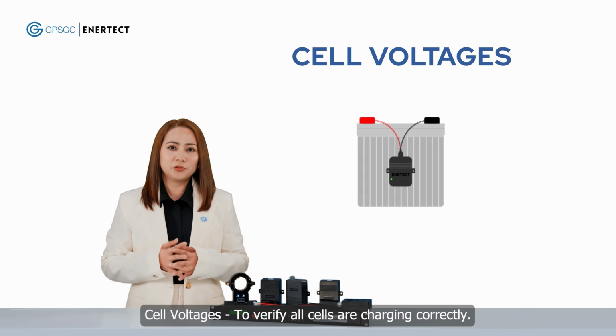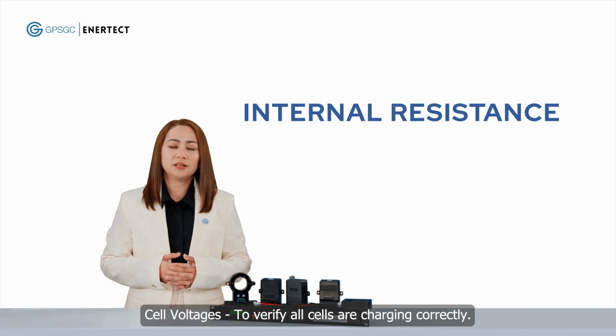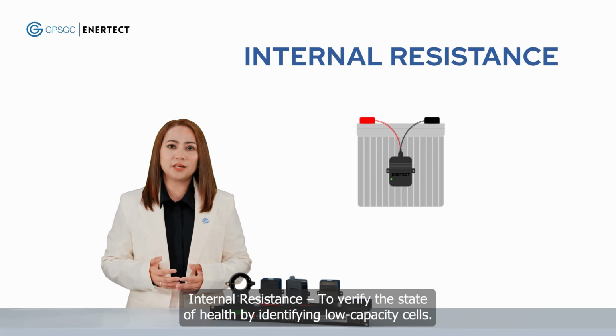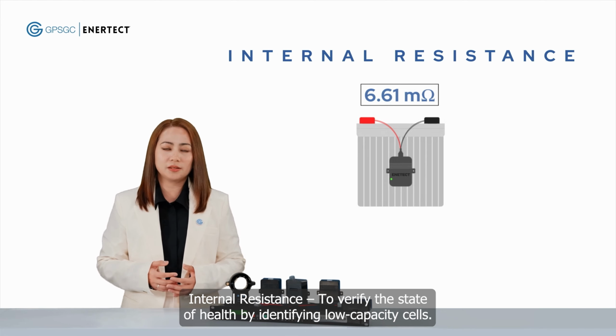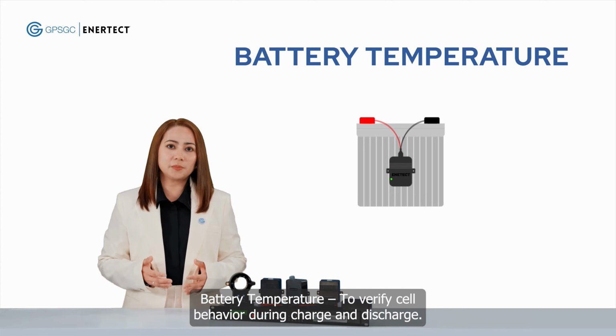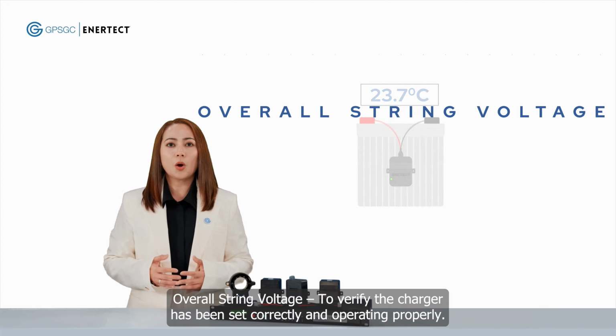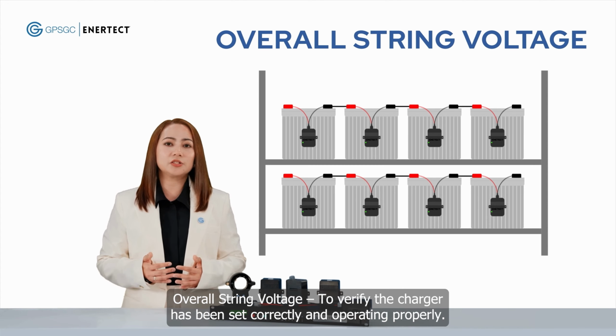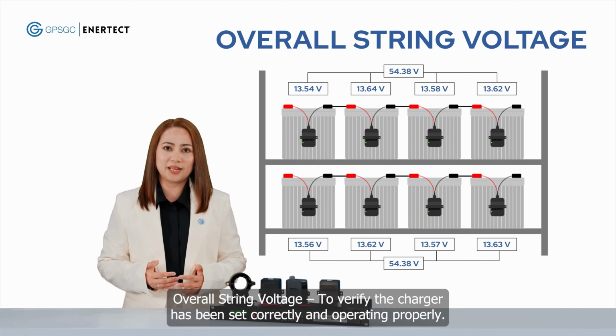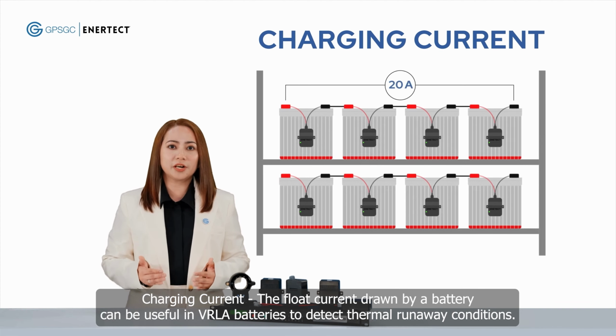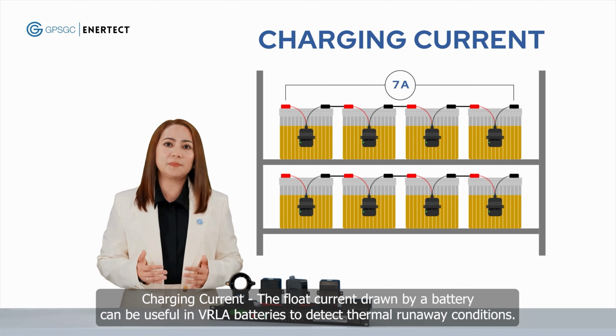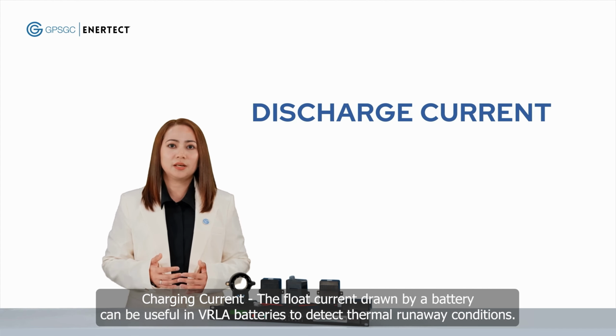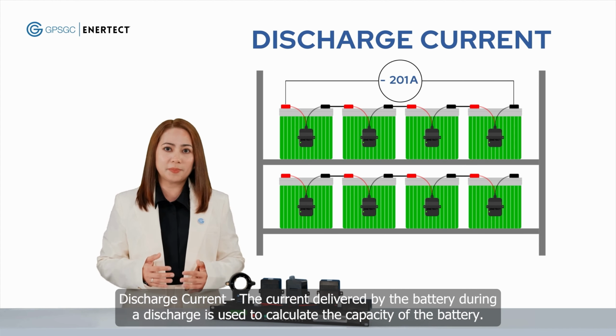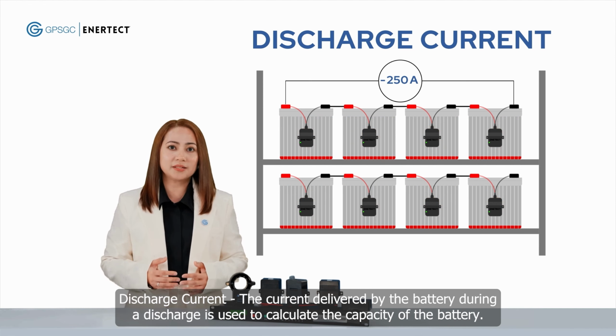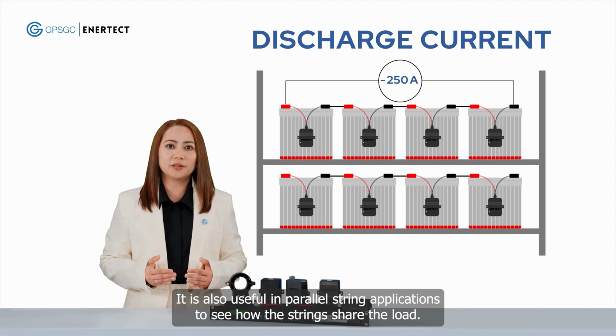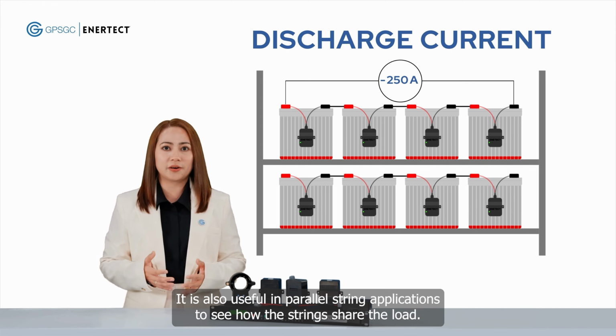Cell voltages, to verify all cells are charging correctly. Internal resistance, to verify the state of health by identifying low-capacity cells. Battery temperature, to verify cell behavior during charge and discharge. Overall string voltage, to verify the charger has been set correctly and operating properly. Charging current, the float current drawn by a battery can be useful in VRLA batteries to detect thermal runaway conditions. Discharge current, the current delivered by the battery during a discharge is used to calculate the capacity of the battery. It is also useful in parallel string applications to see how the strings share the load.